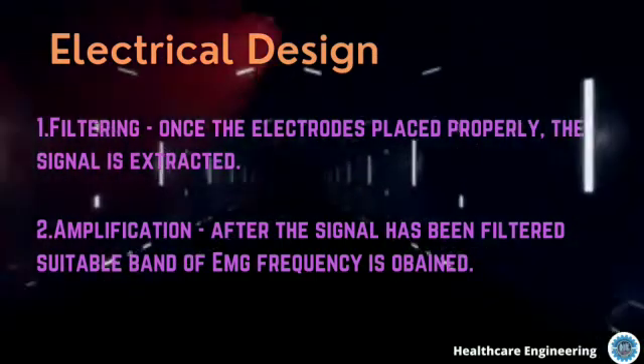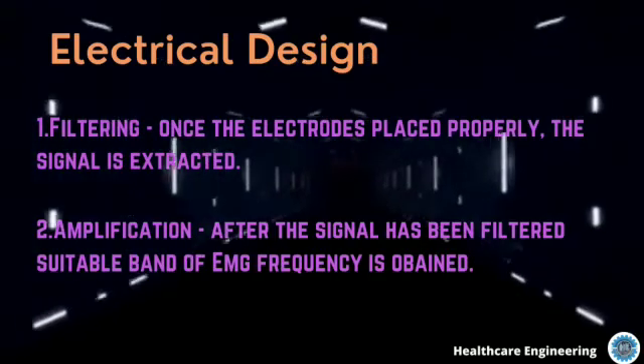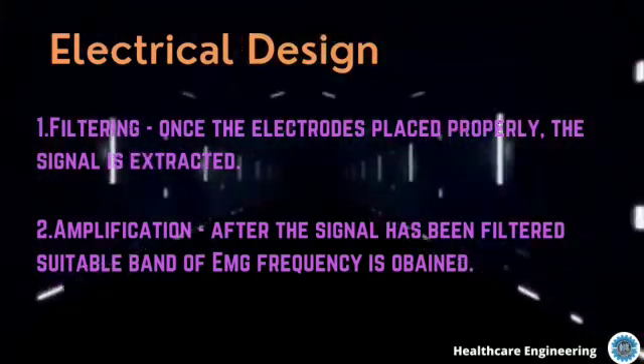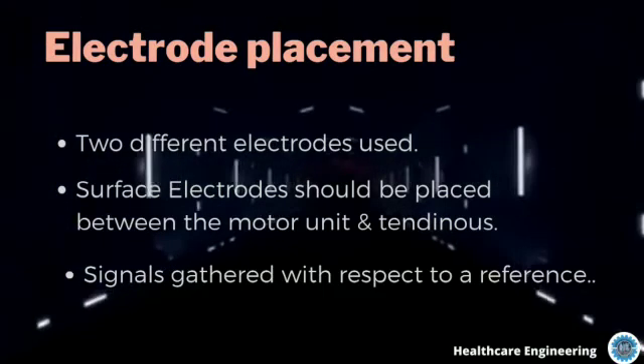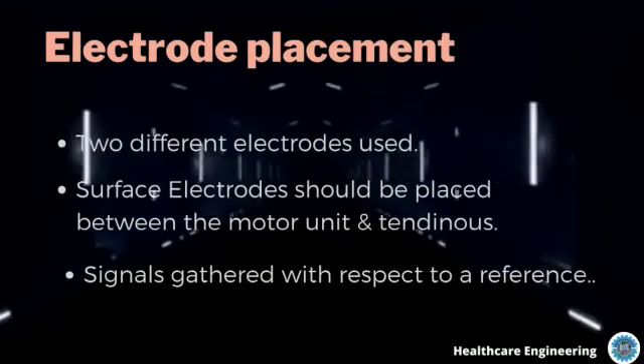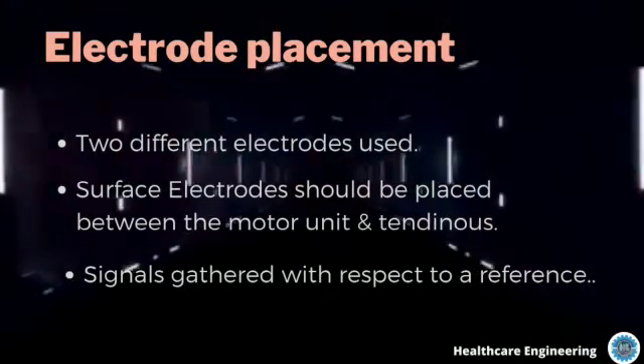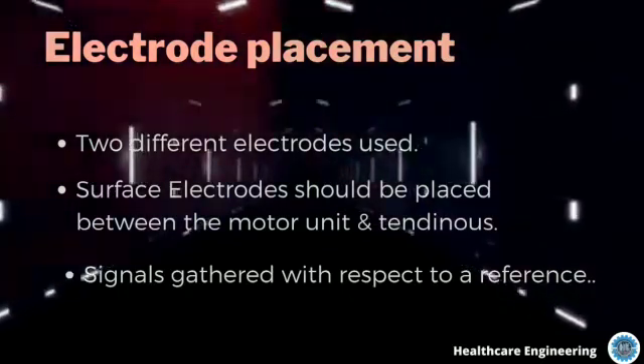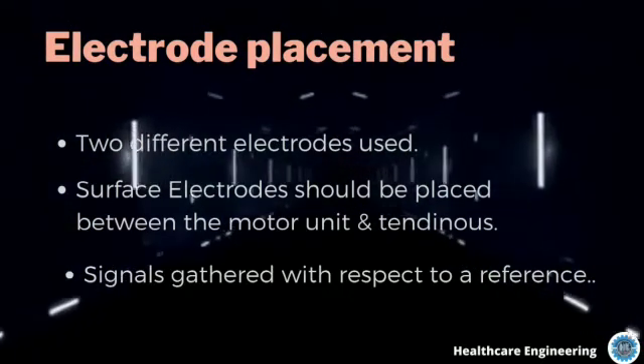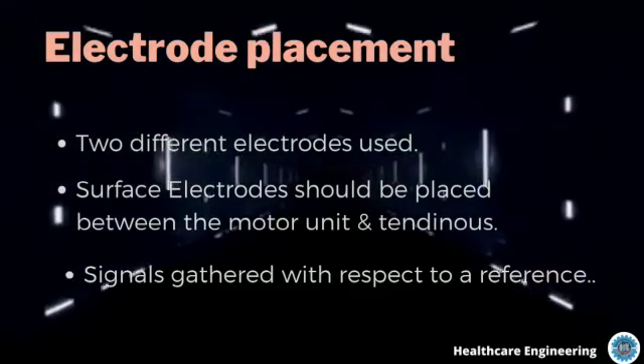After the signal has been filtered properly and a suitable band of EMG frequency is obtained, the next stage is amplification. The amplification of the EMG signal can be carried out with the help of a non-inverting amplifier. Regarding electrode placement, in most cases two detecting surface electrodes are placed on the skin in bipolar configuration. They should be placed between the motor unit and the tendinous insertion of the muscles to get the best possible signal. An EMG reference electrode acts as a ground for this signal and should be placed far from the EMG detecting surface electrodes on an electrically neutral site.